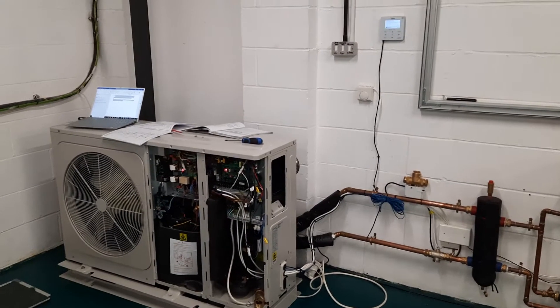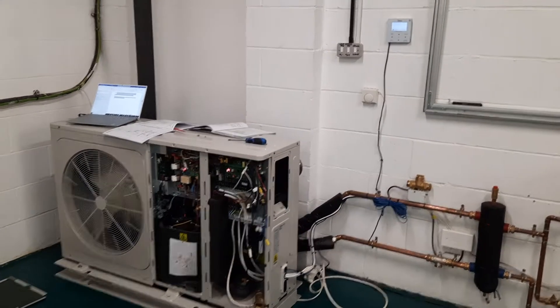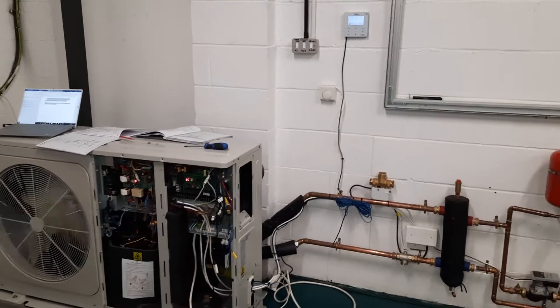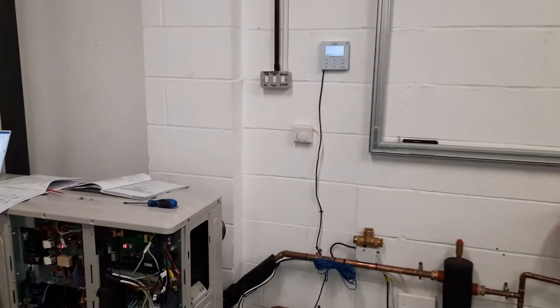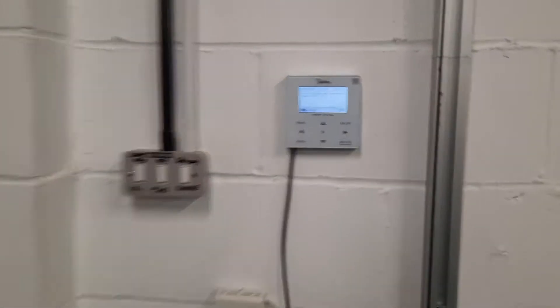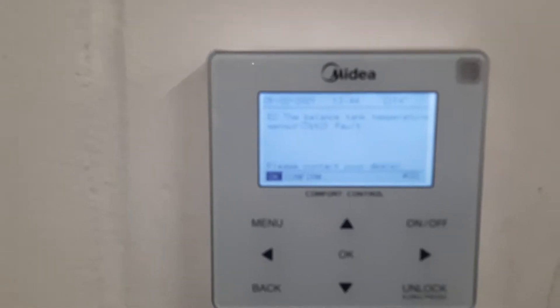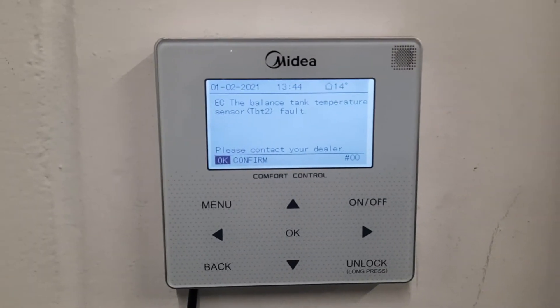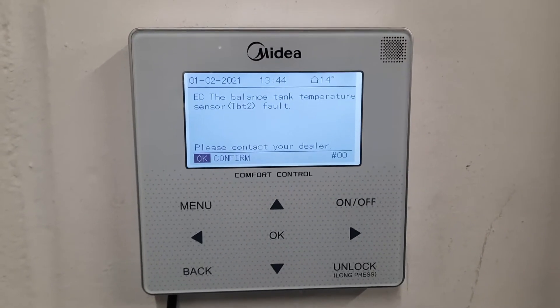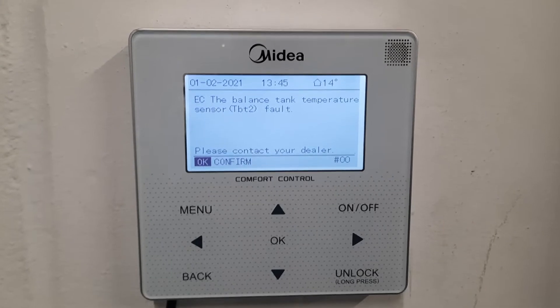In this video I want to show you a fault code on a Midea air source heat pump. The fault code is EC. EC is a very strange fault code — if you look at the remote controller it says EC: the balanced tank temperature sensor TBT2 is faulty.